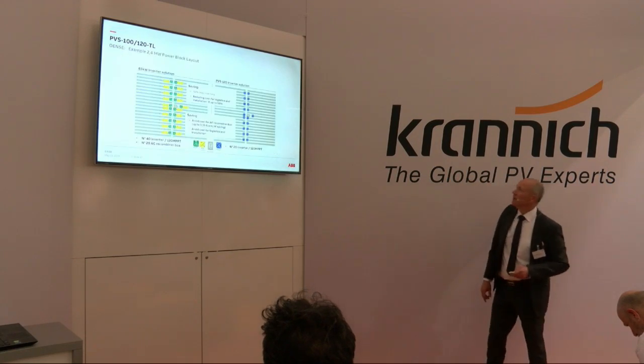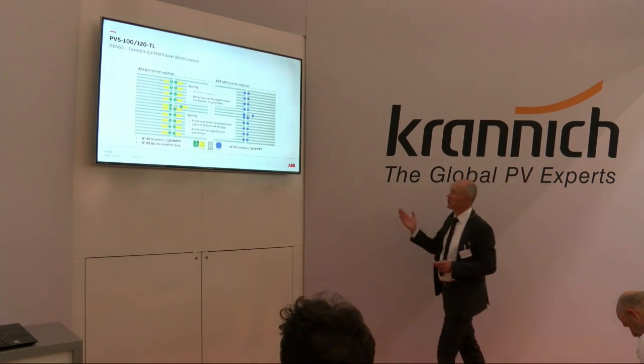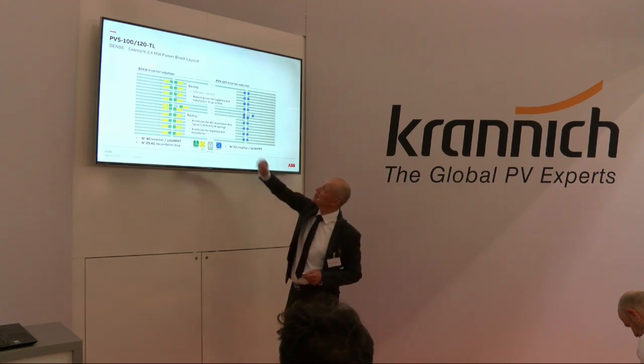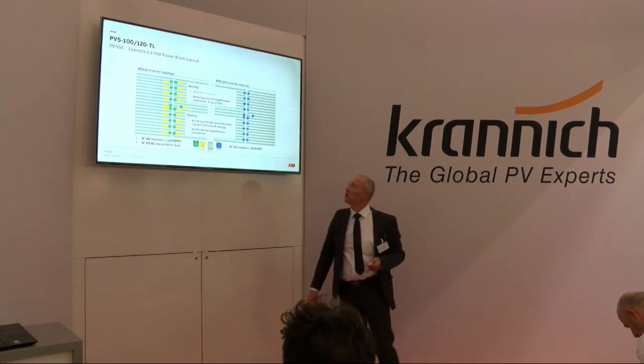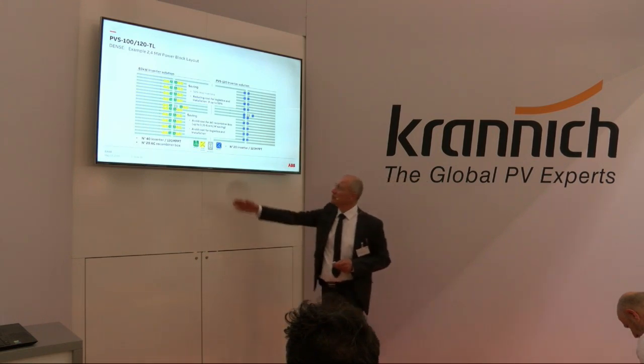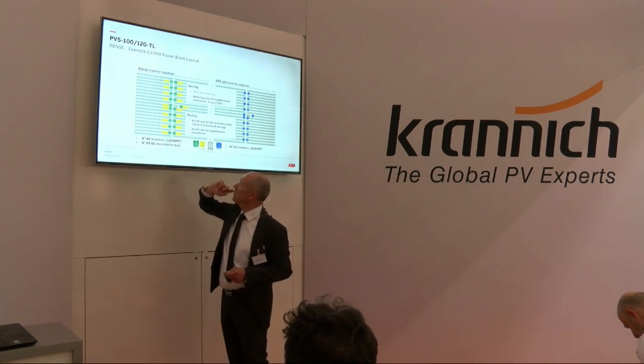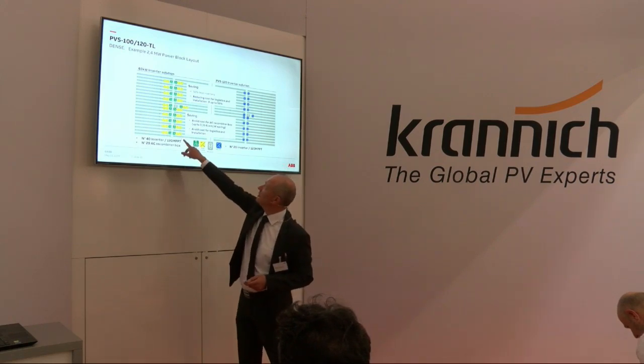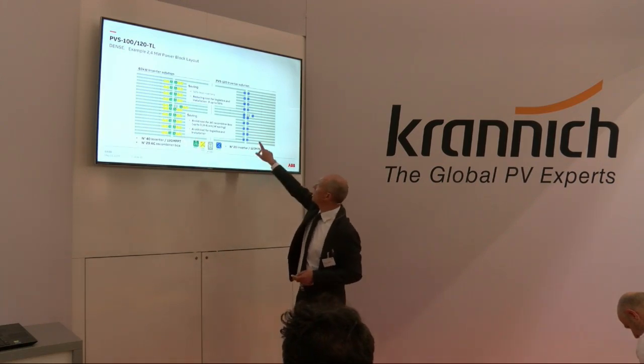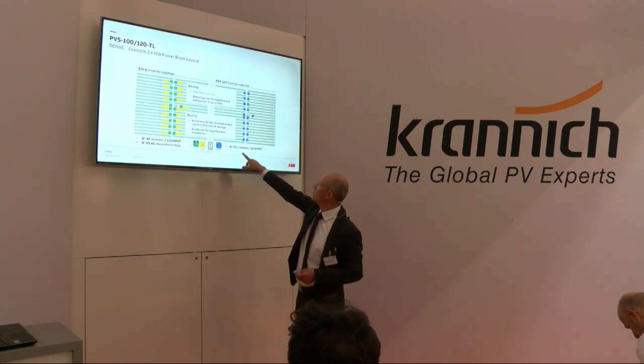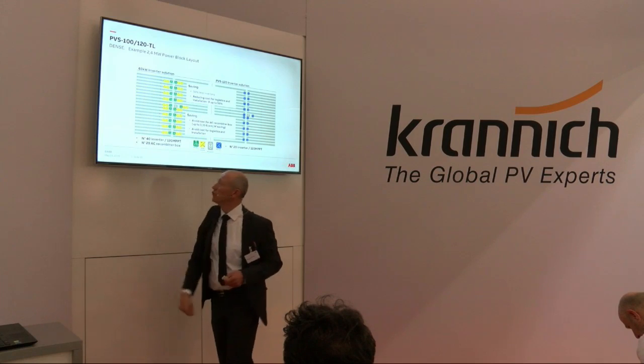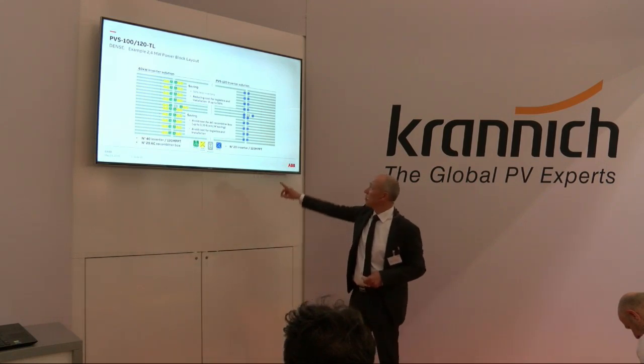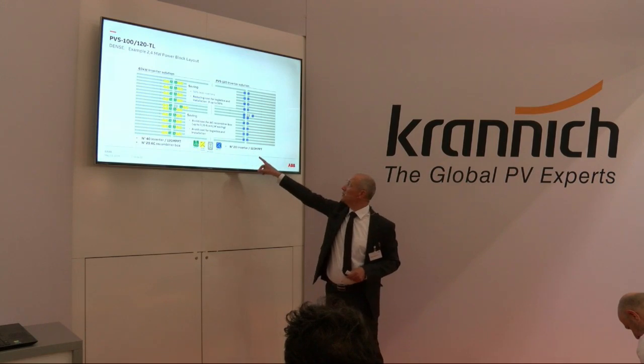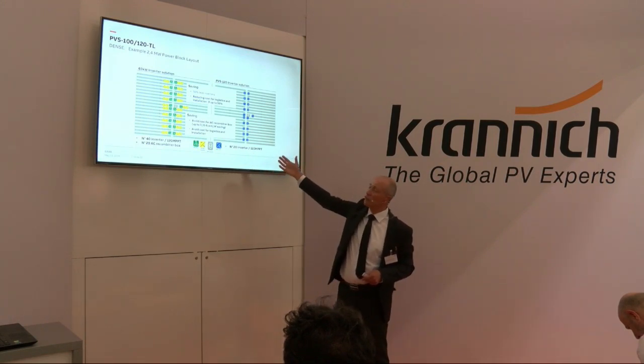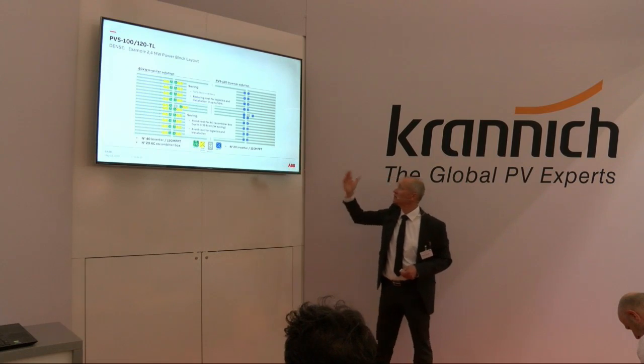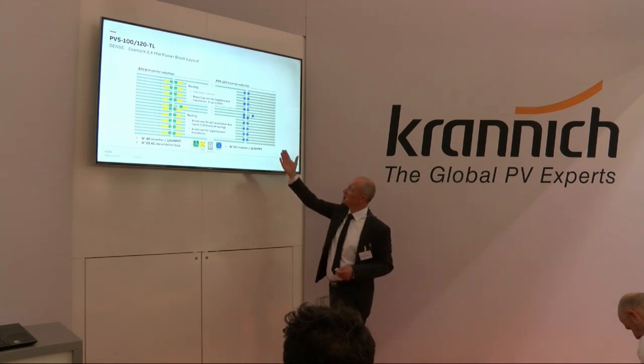Okay, let's go ahead. One advantage is if you're looking for, let's say, a plant size of 2.5 megawatt power block layout, then let's say the largest inverters on the market are around 60 kilowatts. We can do it with 20 inverters, where here you have to do 40 inverters. This means we have 20 pieces only for AC and DC cabling, saving cost, saving time. We have less commissioning, less servicing.